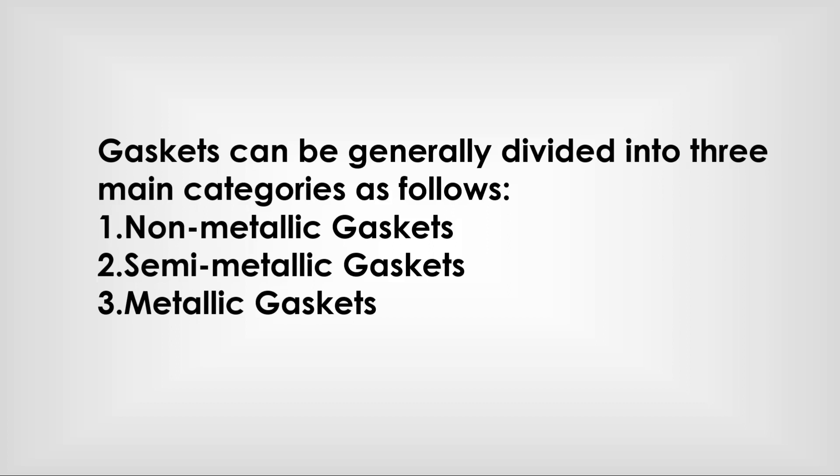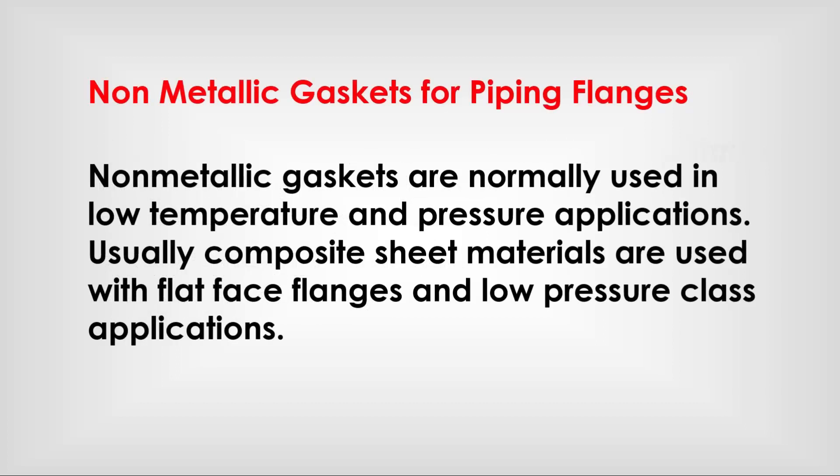Gaskets can be generally divided into three main categories: non-metallic gaskets, semi-metallic gaskets, and metallic gaskets. Non-metallic gaskets for piping flanges are normally used in low temperature and pressure applications. Usually composite sheet materials are used with flat face flanges and low pressure class applications.